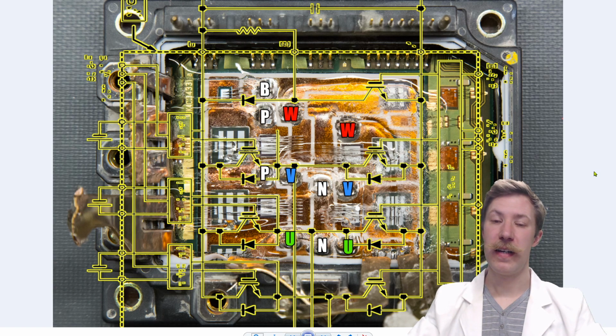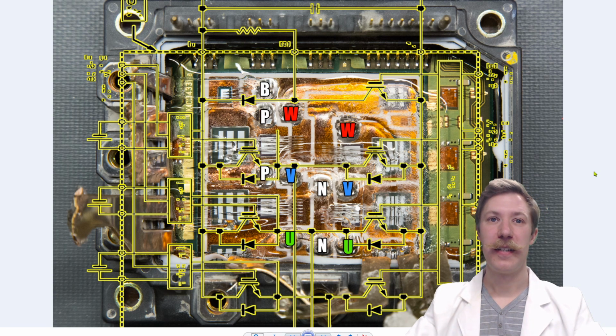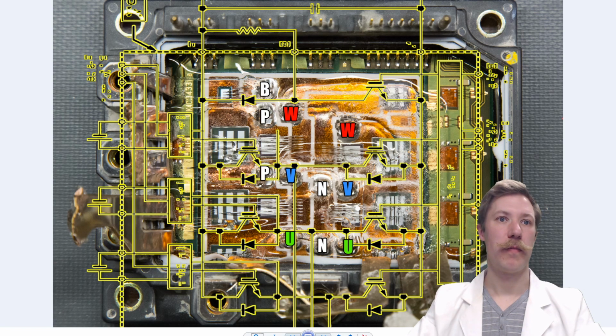I flipped it horizontally, and it actually fits down onto the IGBT brake module. Just look how the braking IGBT up here with the diode, we have the low side, high side, low side, high side, low side, high side IGBTs with its anti-parallel diodes as well. Even the pre-driver markups here are actually fitting right over top of the pre-driving circuits out here. So that's actually quite interesting that the schematic they drew up in the datasheet is quite like the layout of the brick itself.